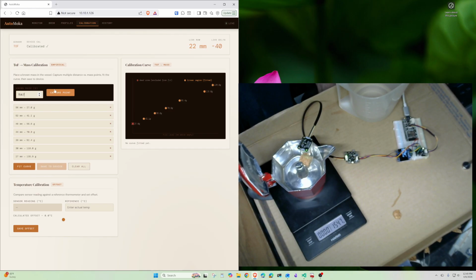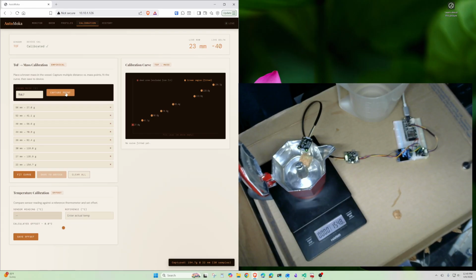You'll see a little delay here when I say capture. That's because I'm capturing the average over a certain period of time. All right, so that's good. We got it, and now we can fit the curve. That does the curve that will be used to estimate, and save it to the device. So we now have the calibration curve saved.